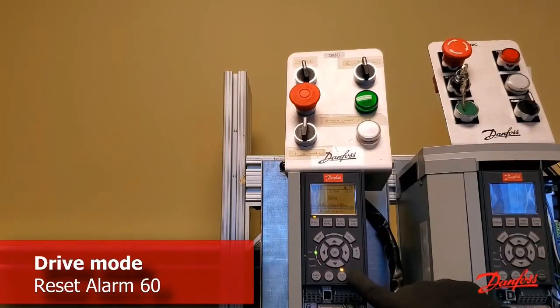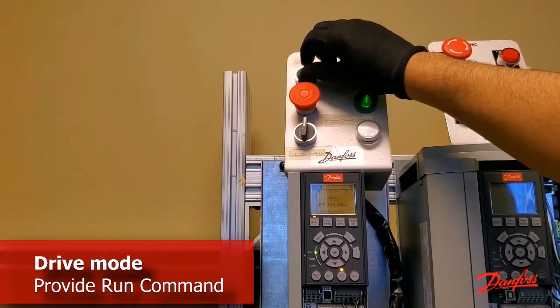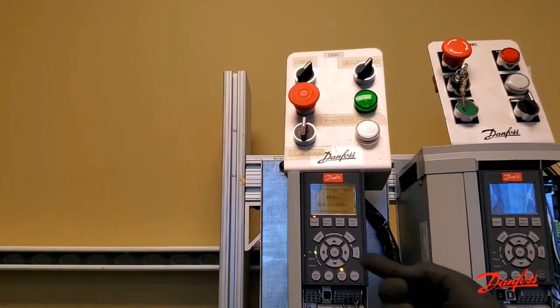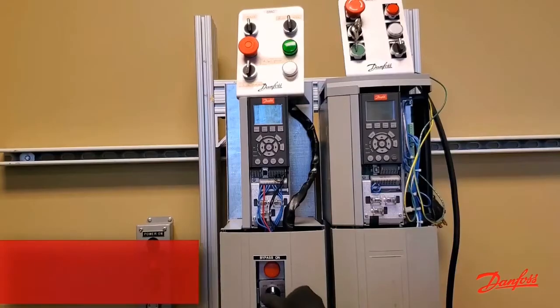The reason for this is simple. We must be able to control and interlock the two systems within the panel, drive and bypass, with a common set of commands. To accomplish this, we use the bypass board as a middleman of sorts.